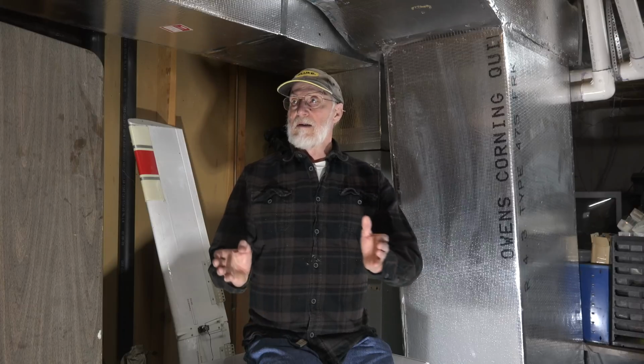Also, in some of the newer furnaces, they have a secondary heat exchanger that's very similar to an air conditioning coil. And I have done a video on cleaning these secondary heat exchangers, because sometimes they will get dirty and you will not be able to determine by taking measurements outside of the furnace of static pressure. It won't tell. It just shows that the furnace doesn't put out very much static pressure. So secondary heat exchangers are one of the things that you're going to need to be looking at when you're running out of answers for what's wrong with ductwork.